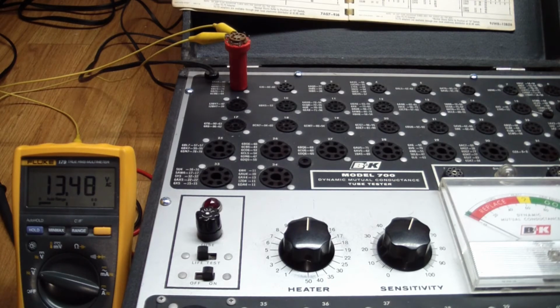So some of the settings actually share the same tap. That's the case here. The 12, 14, and 15 setting all share the same tap on the transformer, which is marked as 12 volts. We are getting 13.4, which is a little higher than 10% off. So that one's good too.